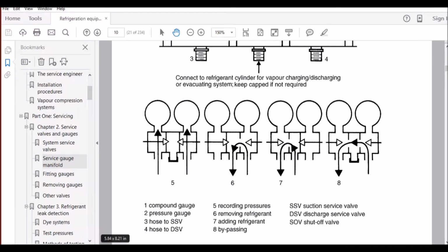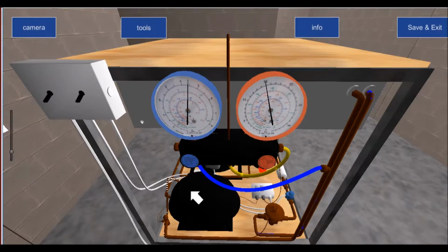And it's very important that we understand that when we go to fit gauges onto a system, we check and make sure that the low side shut-off valve is in the closed position, the high side shut-off valve is in the closed position, the rubber seals at the end of the hoses are in good condition, and that the yellow service hose is actually sealed and fitted to a blank port on the manifold. Usually on the manifold, it can be on the side like this one or on the back of the manifold. And once we've checked all of that, we go back to calibrating it and making sure that our gauge lines are sitting at 0 and 0. So again, we check for all that.